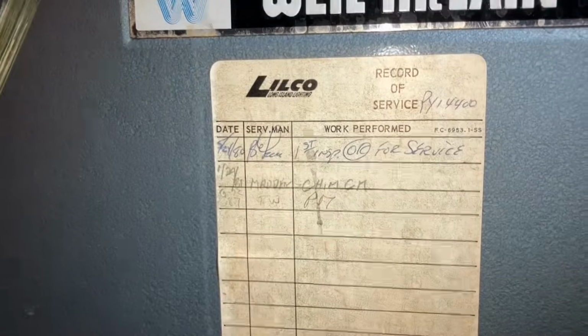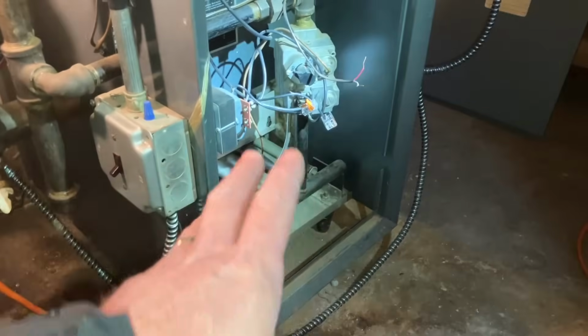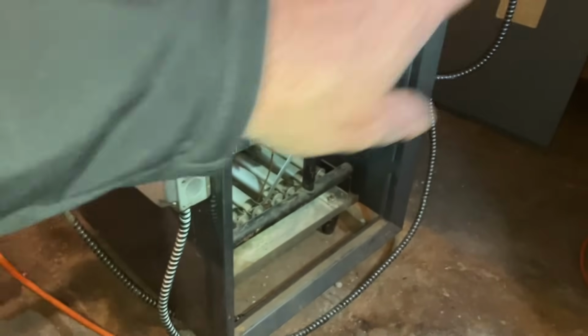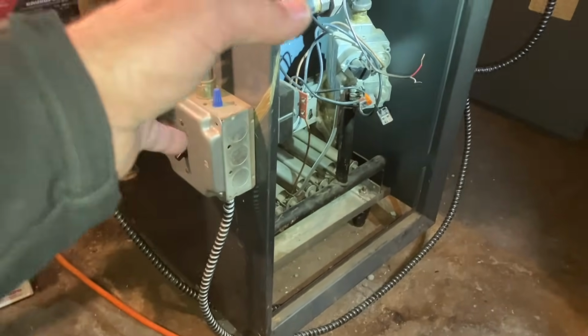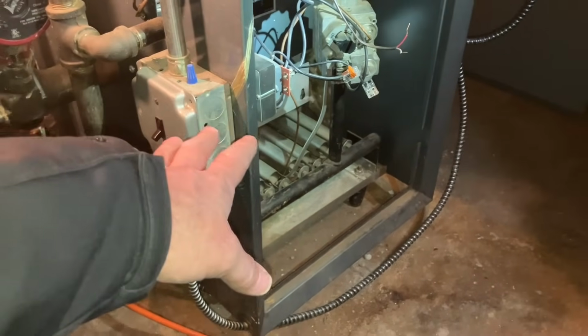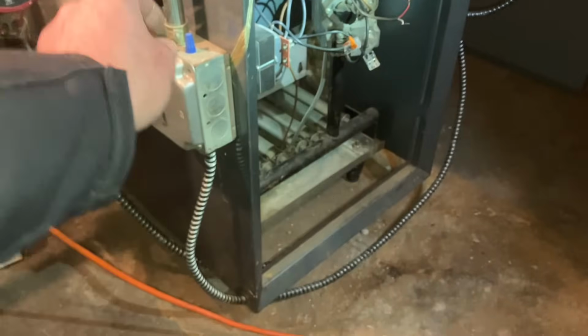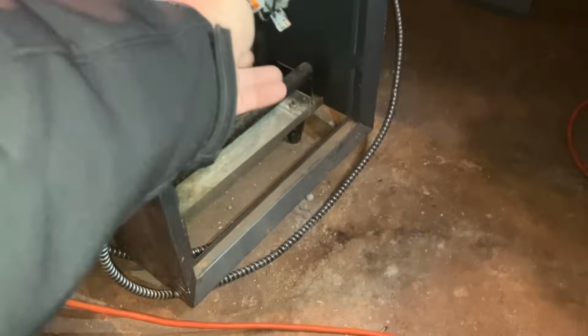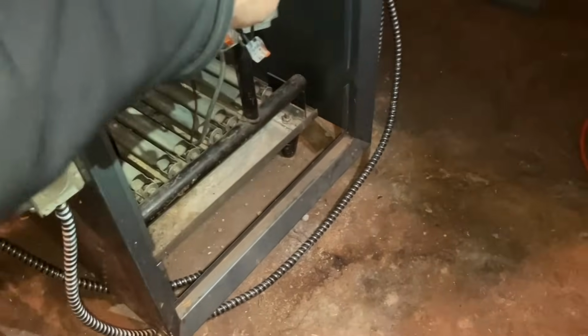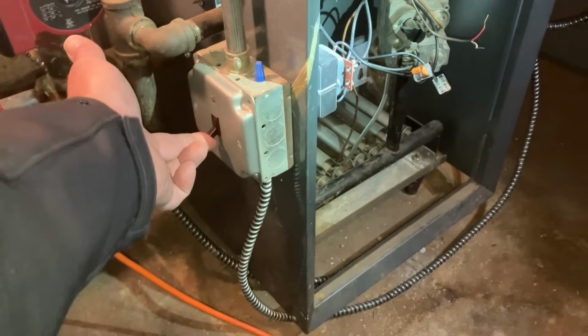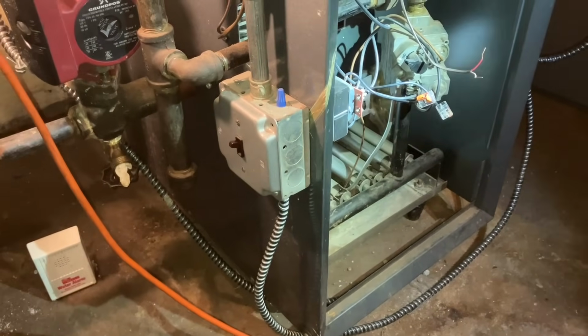There you go, 212355586. That's the date code. 86. When was this being put in? I know 80. I don't know. All right, but because you had mentioned taking the cover on and off, and it did things to the boiler, every connection that I'm working with, I am upgrading the wire nuts and recutting the insulation off. So at least whatever else happens, it shouldn't be due to a bad electrical connection.